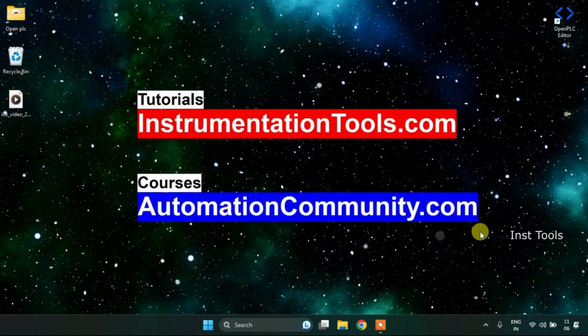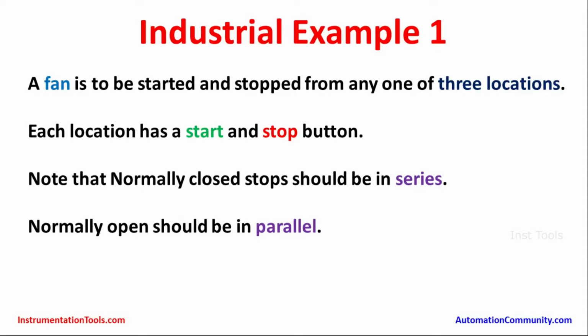We're going to see an example. First of all, we would look at an example. So here is the example, which is industrial example first. A fan is to be started and stopped from any one of the three locations. Each location has a start and stop button. Note that normally closed stops should be in series and normally open should be in parallel.